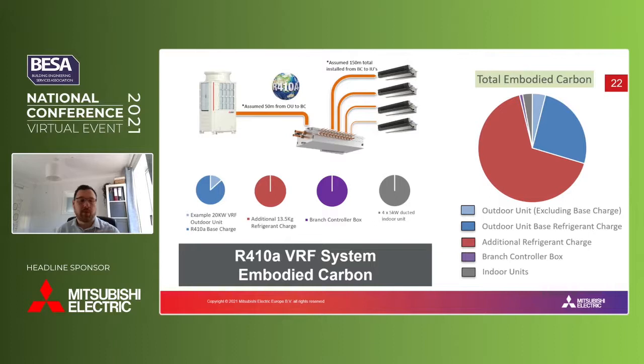The purple pie represents the embodied carbon of the branch controller, one of the components, and the grey pie represents the 4 times 5 kilowatt indoor units delivering heating and cooling attached to a 20 kilowatt VRF outdoor unit. As you can see, the large additional refrigerant charge of R410A, with its relatively high GWP of 2088, is contributing around two-thirds of the total embodied carbon of this example VRF system.